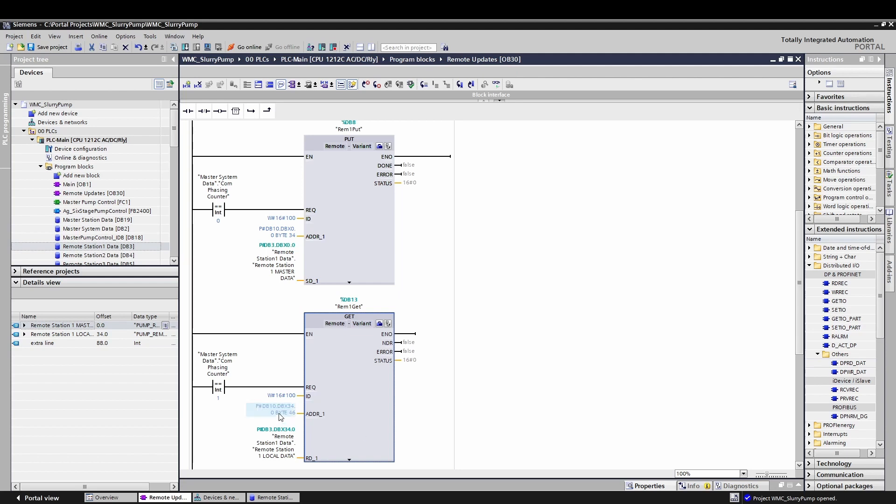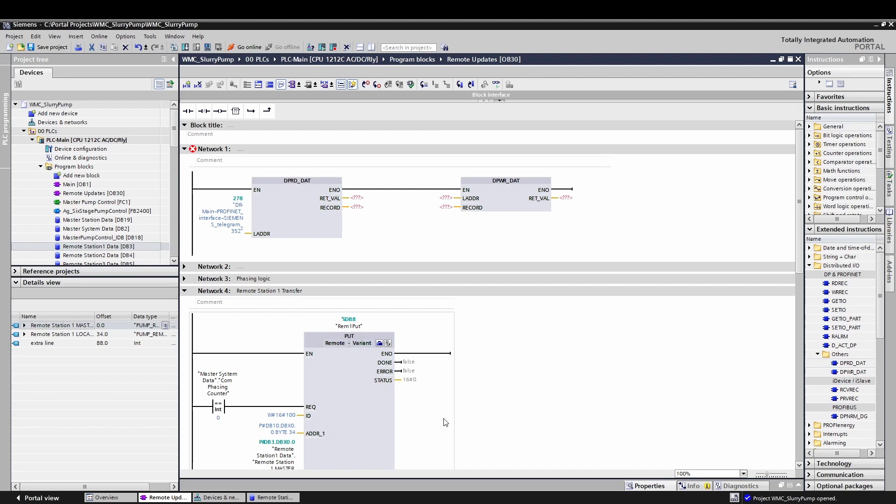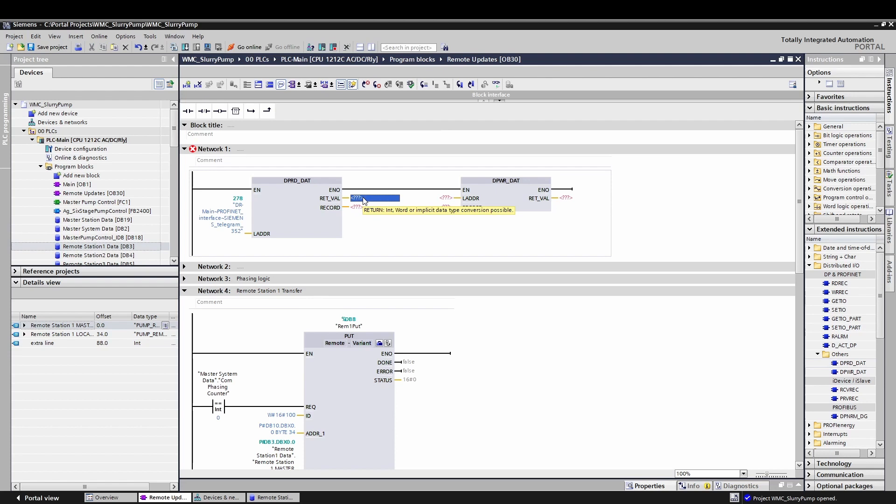So that's it. Once you've determined how your record should be named, you're done. These blocks will handle everything else. I would recommend tying at least a temporary variable to the return value output. Because if something goes wrong in the communication, an error code will be shown here. And you have to have a tag to see the value if you are monitoring the block. There are also ways to use the trace function to record this error parameter. The list of error codes and their meanings are available by clicking on the block and pressing F1.